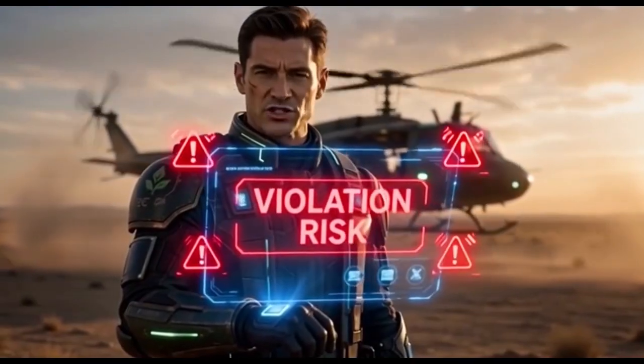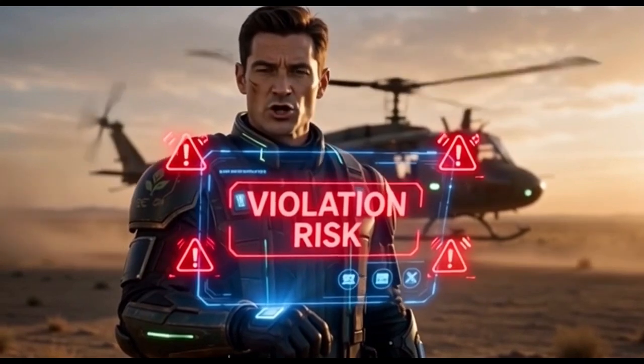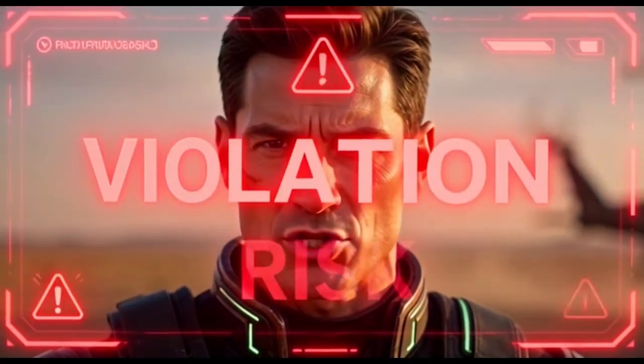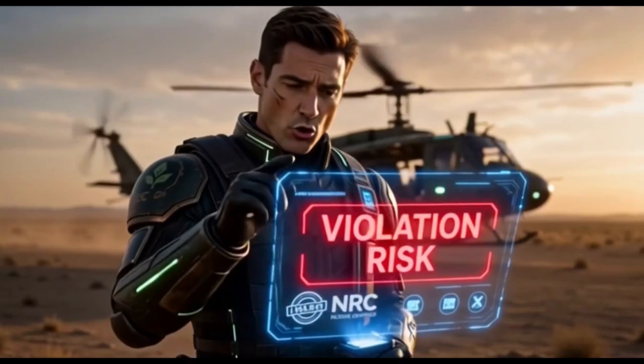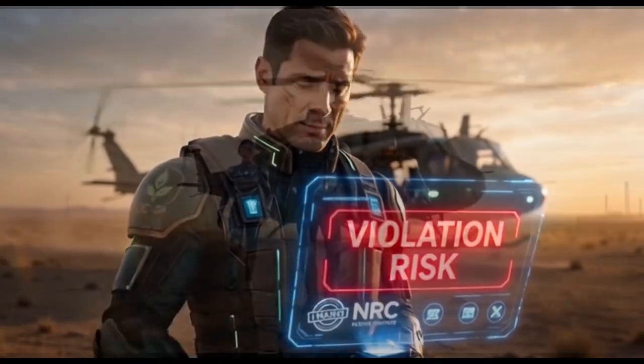Log everything. If you go over the 50 or 100-hour totals or use the engine for any forbidden non-emergency purpose, your generator loses emergency engine status. That means it has to meet the much stricter non-emergency engine rules, which these engines usually don't meet. That's a Clean Air Act violation. Don't risk your mission or your unit. Stay under the limits. All right, team, that wraps it up.